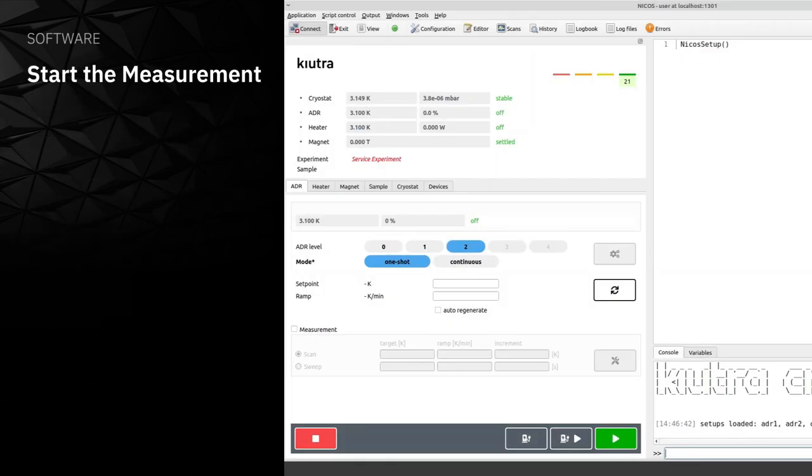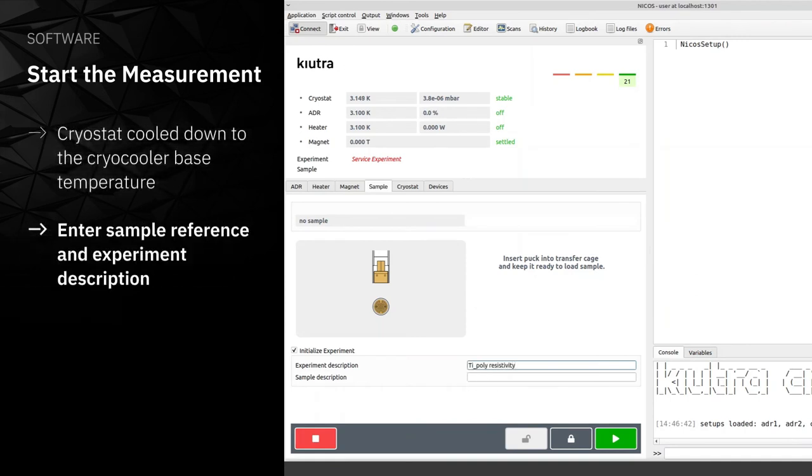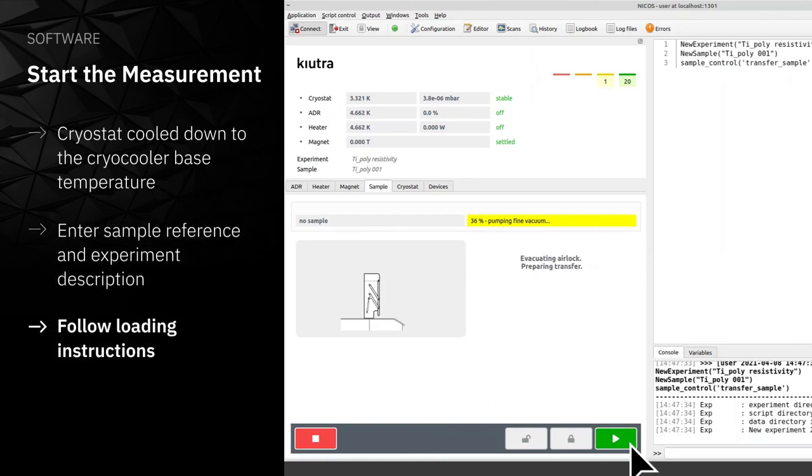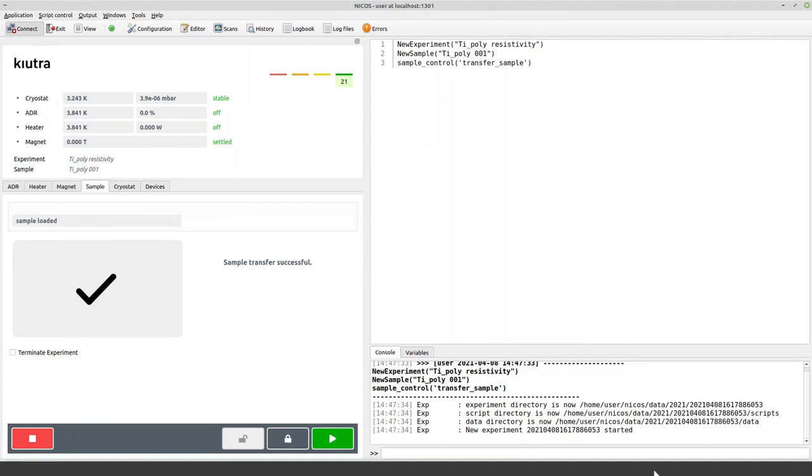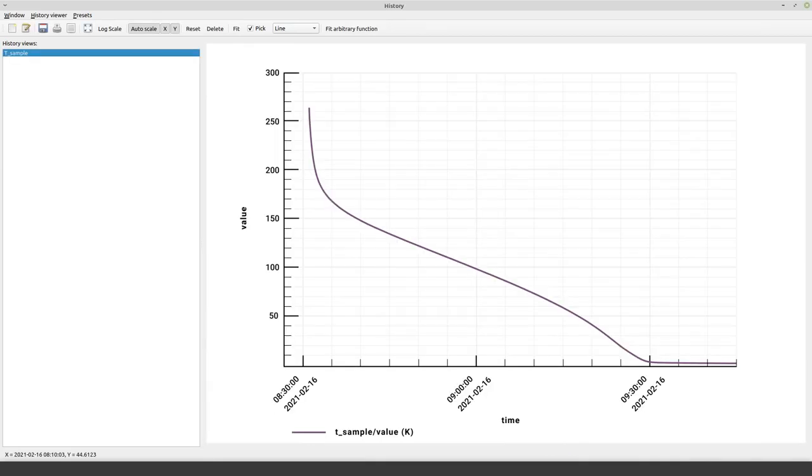So let's start an experiment. In our example, the Cryostat has been cooled down to the Cryo-cooler base temperature and we now want to start an experiment by loading our sample puck. We move to the Sample tab and enter a sample reference and experiment name. Then we hit the Load button and the software guides us through the sample loading process. After finishing the process, we can monitor the cooldown of the sample puck in the History Viewer. By navigating to History and selecting the appropriate time duration and thermometers, we monitor the cooldown of the puck until it thermalizes at the Cryo-cooler base temperature. This process takes around one hour.